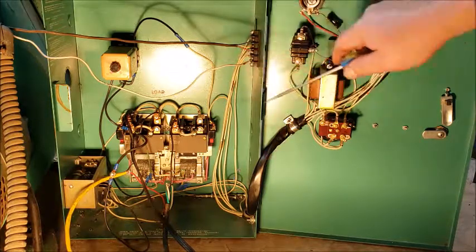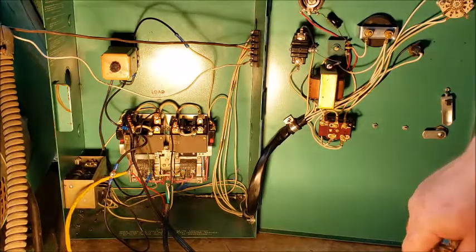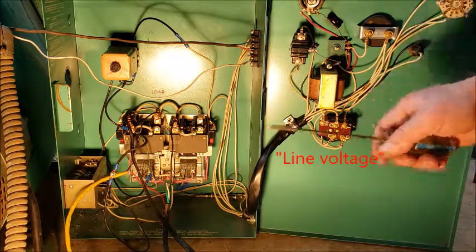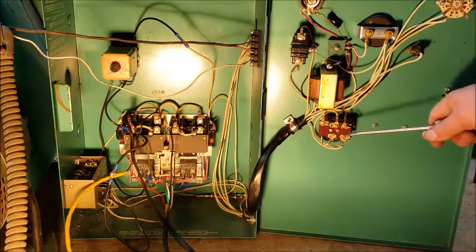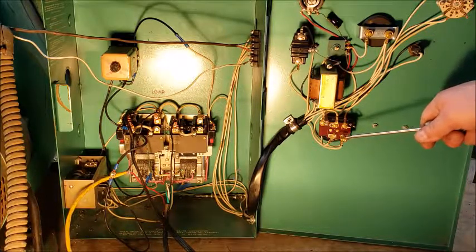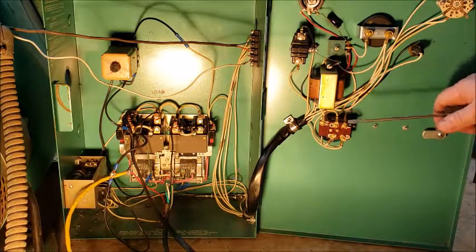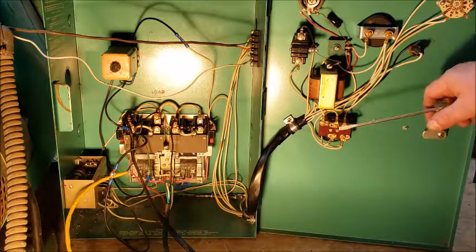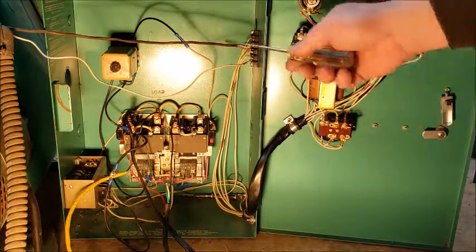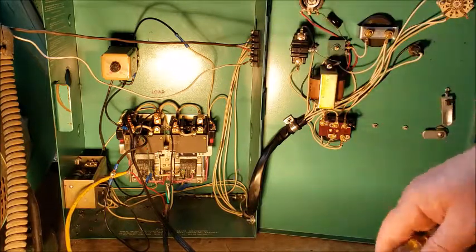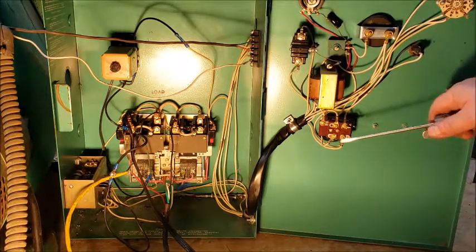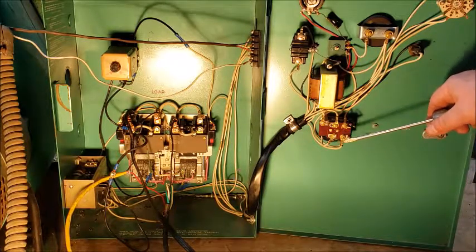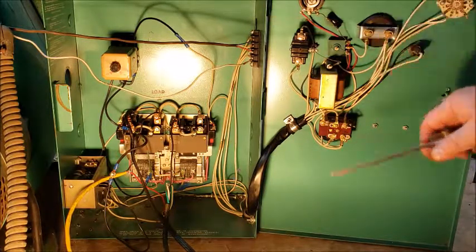So when there's no power this is de-energized. This start disconnect switch or relay, and this I call it a start-stop relay, this terminal and this terminal are hooked together, and so then that grounds out that circuit. 115 volts comes into play, this circuit or this relay energizes and it connects this terminal and this terminal together and that goes directly to the stop wire. So when you have 115 volts of line voltage this relay energizes and stops the generator.